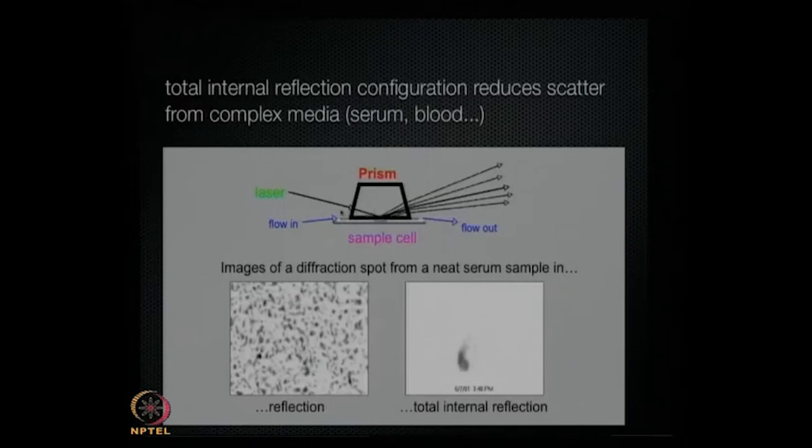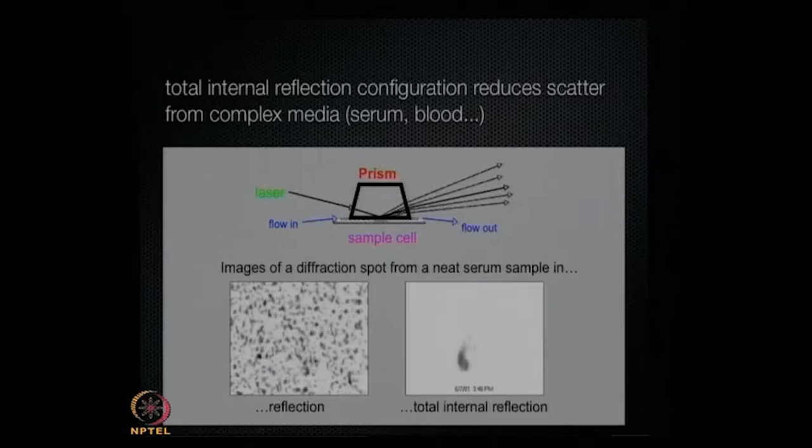The role of the prism is to make sure that the light beam doesn't get scattered by whatever is in solution. Here's a picture of what the diffraction spot would look like if there were no prism — if it's not under total internal reflection. With total internal reflection, we get it a lot cleaner. That means you can actually use a fluid like blood or something equivalently murky. Measuring blood or serum is very important for diagnostics, and measuring that is very challenging because of scattering. Even if you're using cell lysate, it has a lot of particles that will scatter light. So you don't have to purify your sample before doing the experiment.